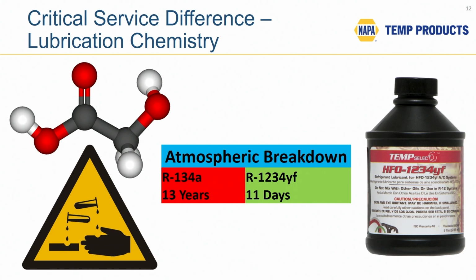And also, critically important, you must use the YF dedicated oil, because while it is still a base PAG, the oil itself has a special chemical additive package to stabilize the chemistry in the system. So it's important to use the new oil with the YF refrigerant. The new oil, however, you can use if it's the same viscosity. Most of them are PAG 46. You can use this oil in an older R134a system, but not vice versa.